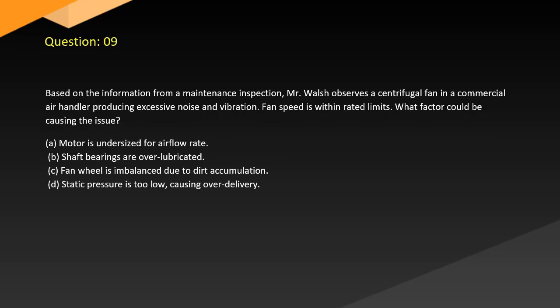Question 9. Based on the information from a maintenance inspection, Mr. Walsh observes a centrifugal fan in a commercial air handler producing excessive noise and vibration. Fan speed is within rated limits. What factor could be causing the issue? A. Motor is undersized for airflow rate. B. Shaft bearings are overlubricated. C. Fan wheel is imbalanced due to dirt accumulation. D. Static pressure is too low, causing overdelivery.